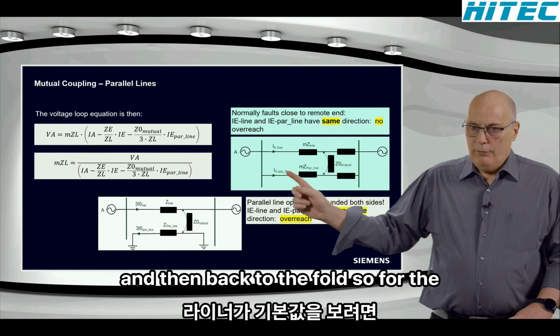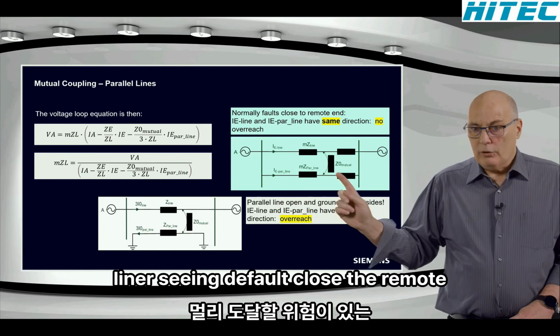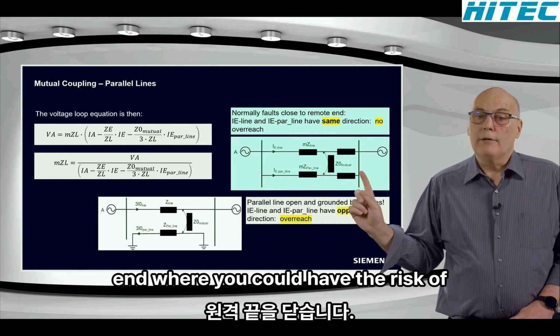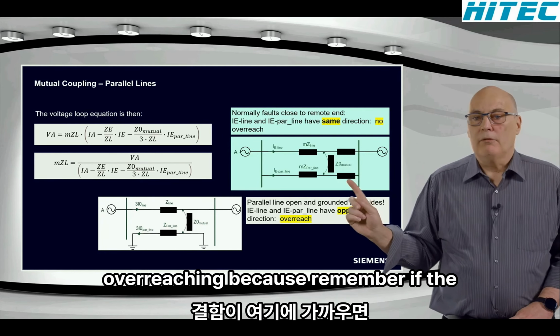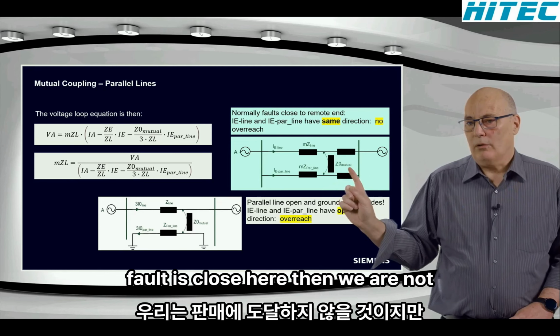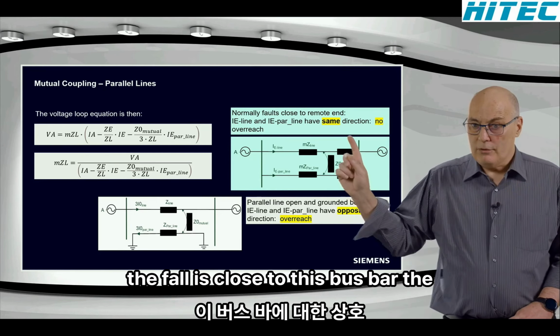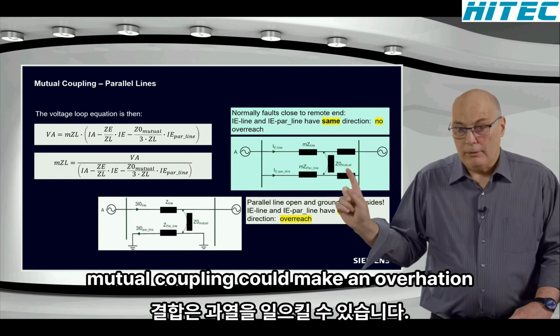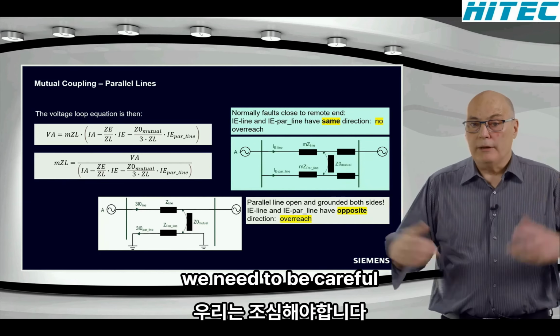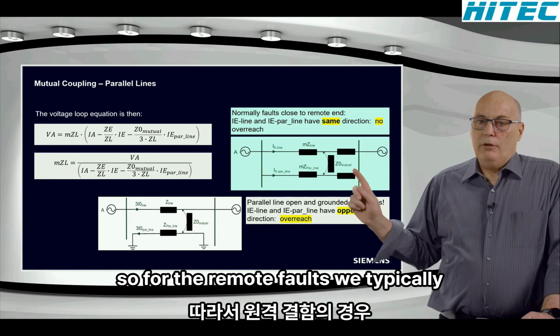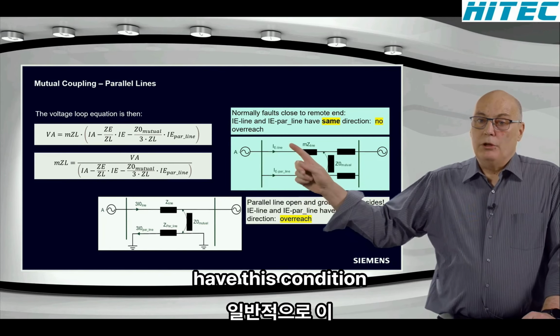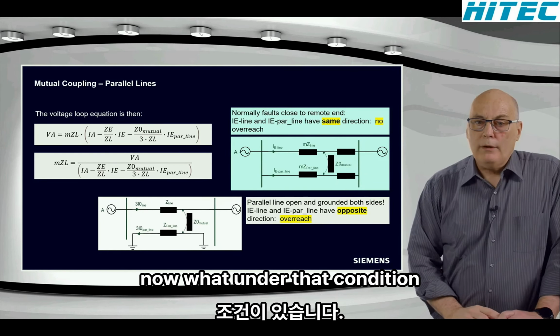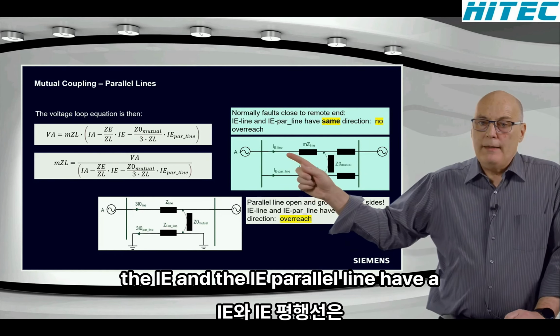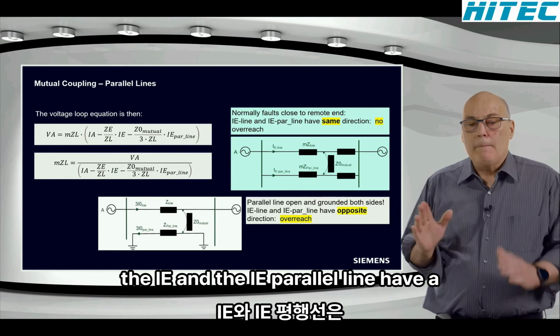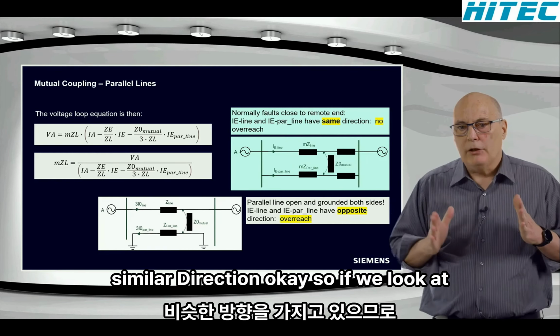So for the line that's seeing the fault close to the remote end, where you could have the risk of overreaching, because remember, if the fault is close here, then we are not going to get overreach this side. But if the fault is close to this bus bar, the mutual coupling could make an overreach, and we need to be careful. So for the remote faults, we typically have this condition. Now, under that condition, the IE and the IE of the parallel line have a similar direction.